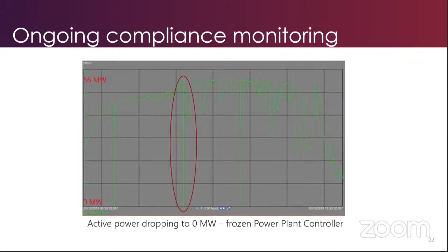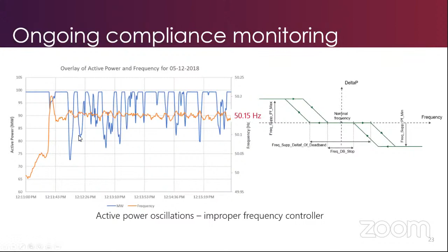Another example to show why it is important to monitor. This is from another solar farm. Its frequency controller was not properly designed or set up. It has a trigger point, but it didn't have a dead band or a hysteresis. As a result, for every movement around the set point, it was making a movement in active power, resulting in oscillations.